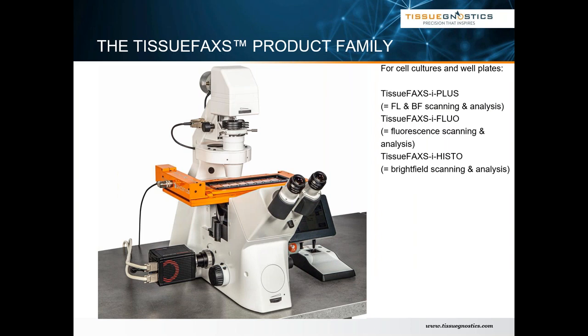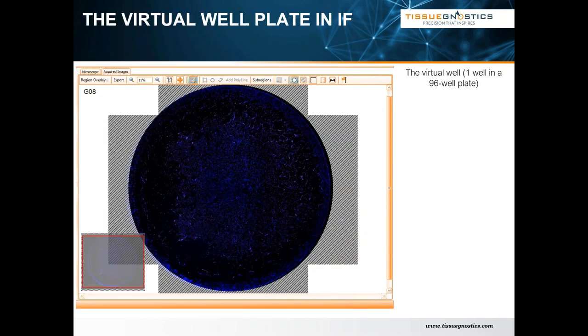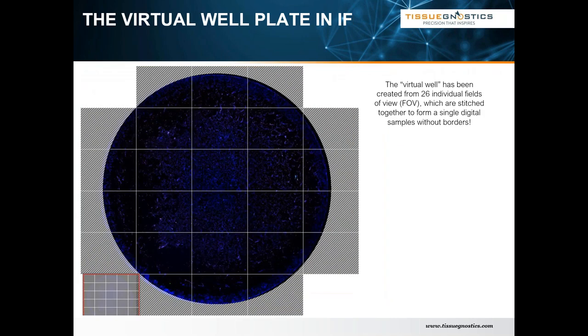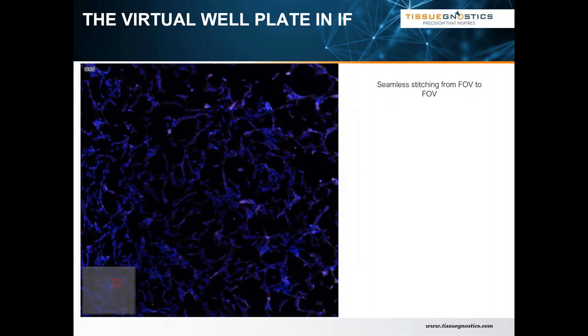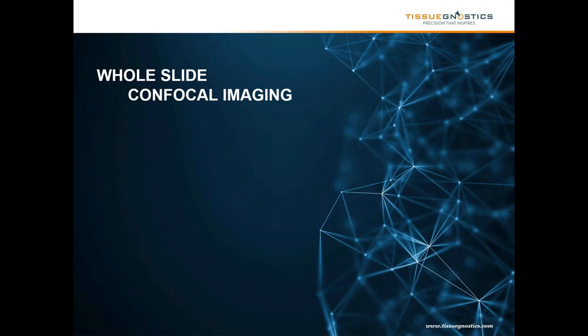Here's another configuration — this is an inverted TissueFAXS system for scanning slides as well as cell cultures and well plates. These can come in a Plus configuration, which usually implies bright field and fluorescent scanning capability. Fluo is only for fluorescence and Histo is one camera only for bright field. So they can come in all these different configurations. The workflow is really what's important here — it allows us to scan slides as well as well plates. Here you can see the different fields of view that are stitched together automatically, and if we zoom in, you really can't see where those images are stitched together.